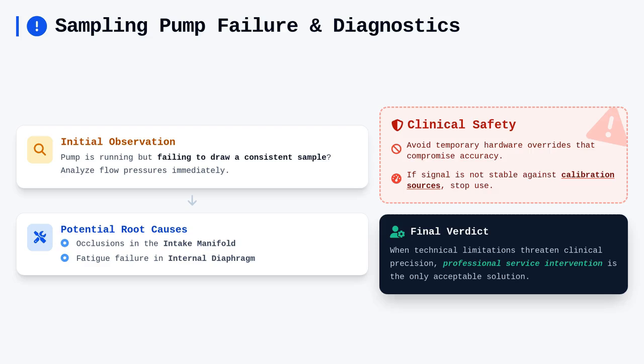Sampling pump failures can bring your diffusing capacity or gas analysis testing to an immediate halt, but they are often solvable through careful observation of flow pressures. If the pump is running but failing to draw a consistent sample, look for occlusions in the intake manifold or a fatigue-induced failure in the internal pump diaphragm. While you might be tempted to implement temporary hardware overrides to finish a current patient, you must always evaluate if such a decision compromises the accuracy of the result. If a bypass or a pressure setting adjustment does not yield a stable, repeatable signal against a known calibration source, you must remove the device from active service immediately. Systematic fault isolation is not just about keeping the machine running. It is about recognizing when the technical limitations demand a professional service intervention to maintain clinical precision.